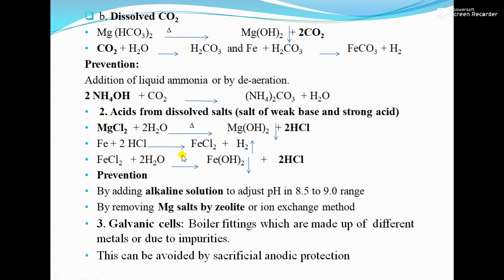This corrosion is due to the presence of magnesium chloride, so we must remove it. The corrosion also occurs due to the hydrochloric acid generated, so we need to neutralize that acid. Prevention: use an alkaline solution to adjust the pH of water to the range 8.5 to 9. To remove the magnesium chloride, we use the zeolite method or ion exchange method, which will be covered in the coming lecture.